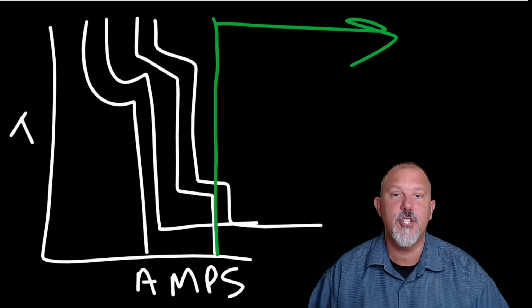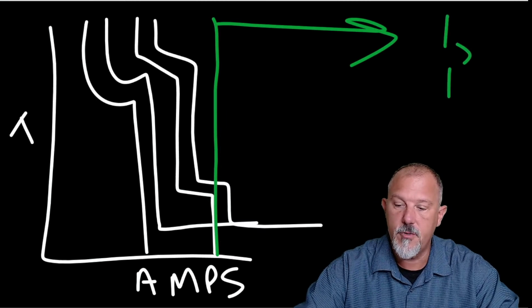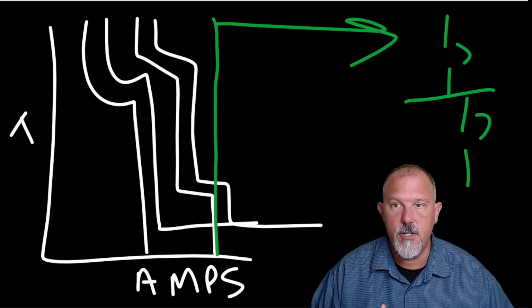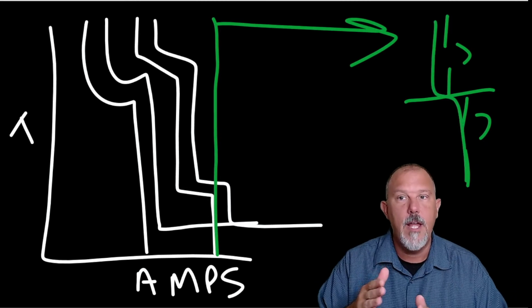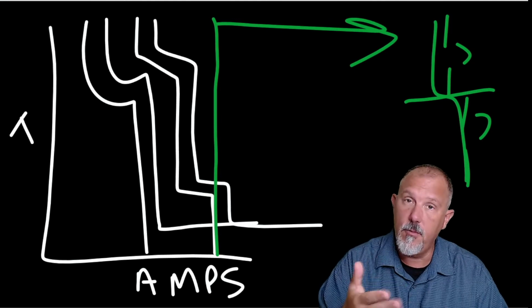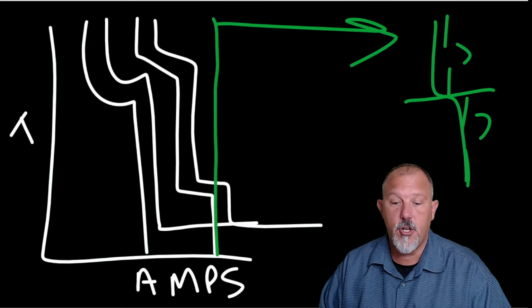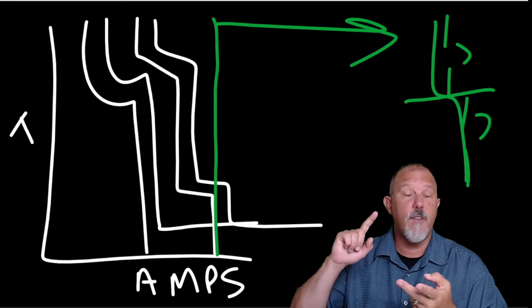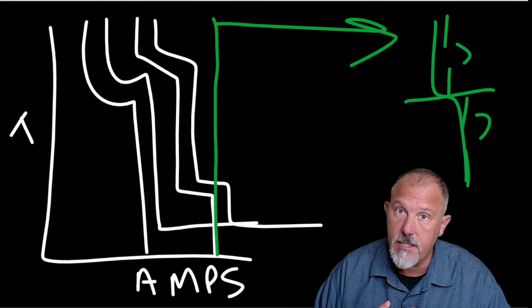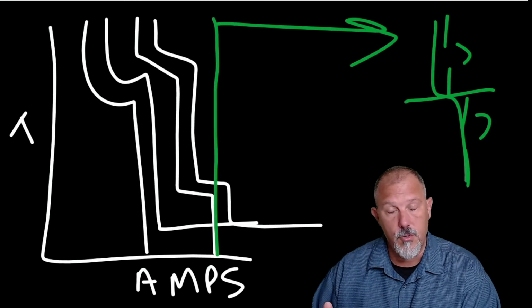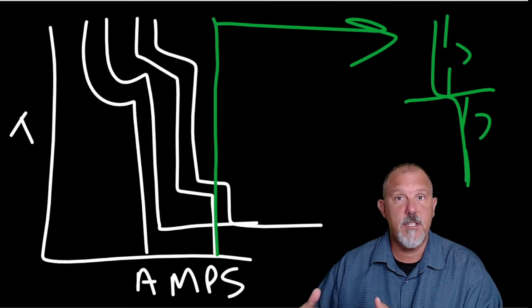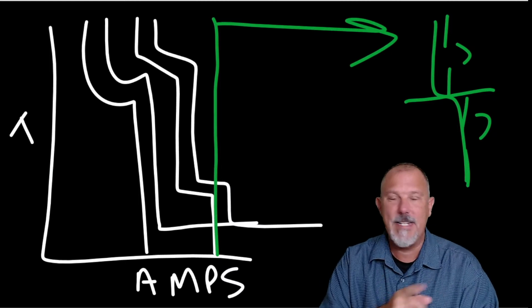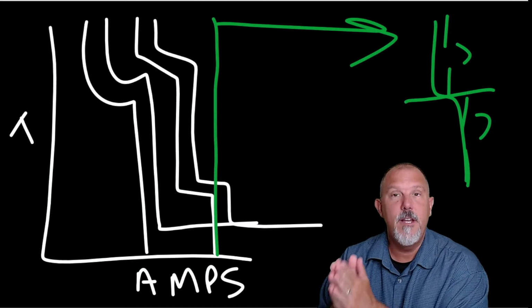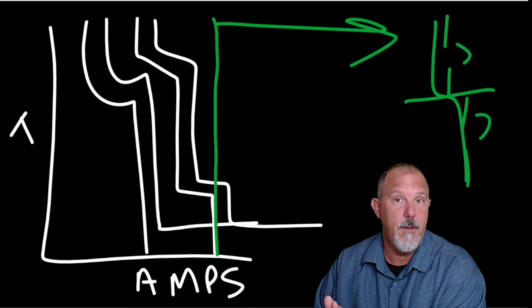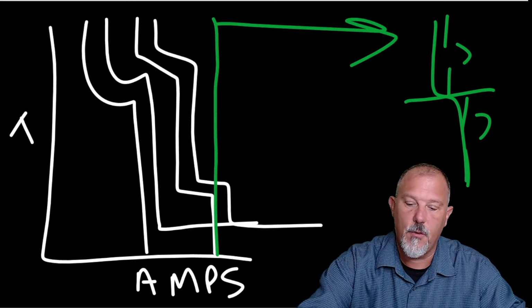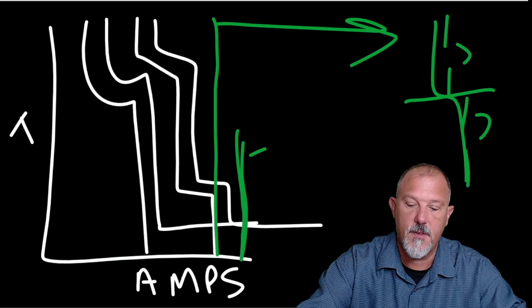selective coordination tables where we actually test pairs of circuit breakers. We have an upstream breaker and a downstream breaker, and we test those together. We push current through both of those, and we know at what point they both open, and then we tell you that number. We say, okay, I don't care if it's a ground fault current, a three-phase bolted fault current, or an arcing current, if current passes through those two breakers persistent enough at a high enough level, based upon the numbers in the tables, then I know they're both going to open. So the green line for that might be somewhere in here, which is based on the tables.